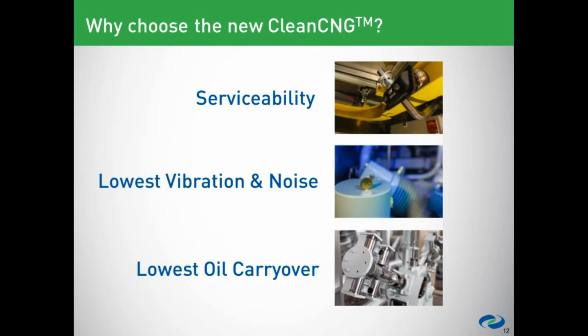Again, the new CleanCNG, its key elements: serviceability, lowest vibration and noise. We've got this down to 75 dB at 3 meters. And again, I've stood beside the unit, unanchored, and had a conversation with it running, literally right beside it. And lowest oil carryover. And with that, I will hand this over to my associate, Brad Neels.